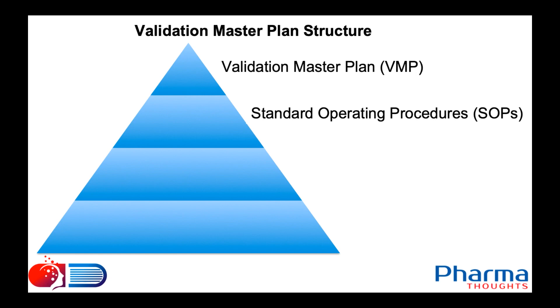Following SOPs, there shall be individual protocols specific to one product or one activity. For example, VMP states that prospective process validation shall be carried out before any product is commercialized. And the SOP on process validation provides details on how validation shall be carried out, how to handle deviations, when the validation is considered successful, etc. Then a product specific protocol shall be prepared to define how the validation will be carried out, what the acceptance criteria are, etc. So an SOP is common for any process that needs to be validated, but a protocol is specific to a process. And finally, a report is prepared to conclude on how the validation activity has taken place and whether the process can be considered valid or not.